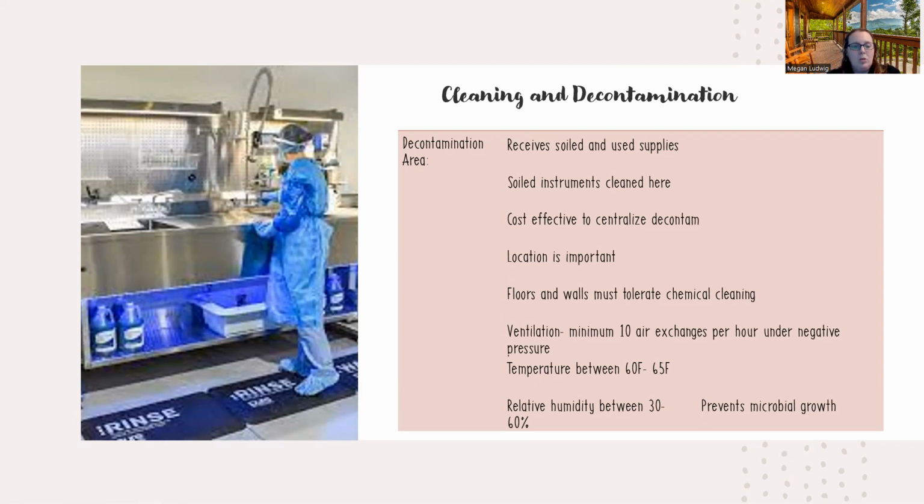It's also under negative pressure, which means as you would open a door to this room, none of that dirty air, so to speak, or contaminated air would go out into the hall. You wouldn't want that. It would stay inside.